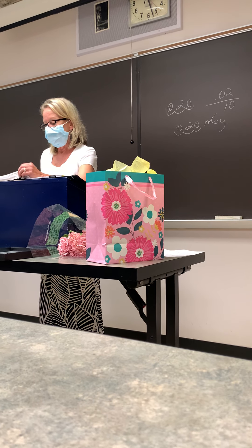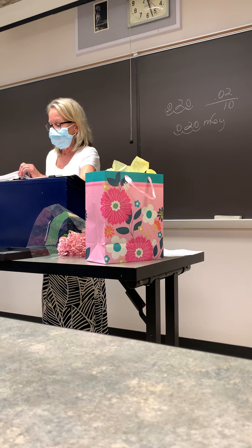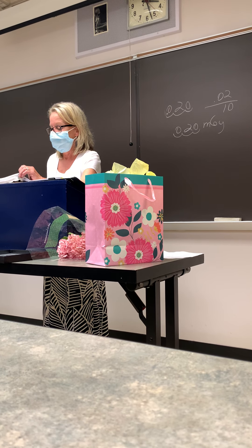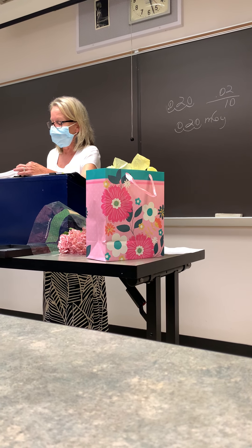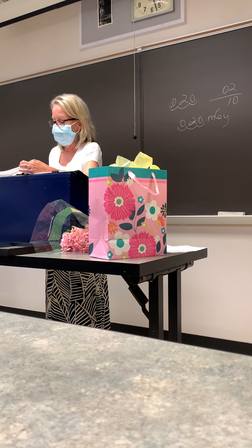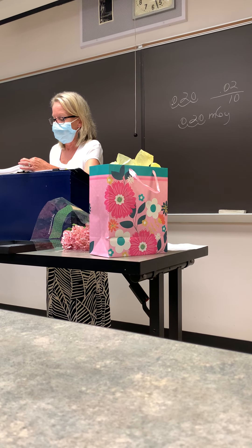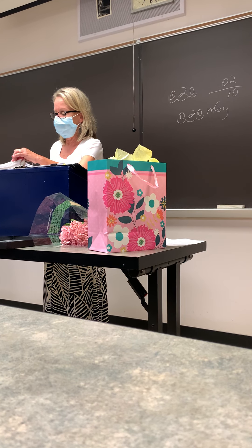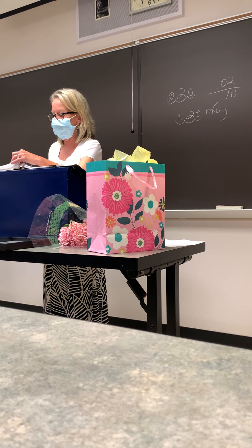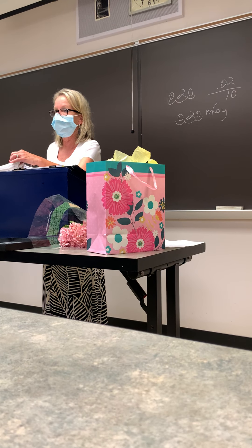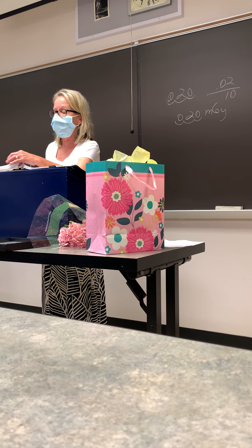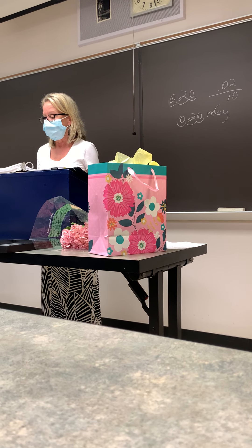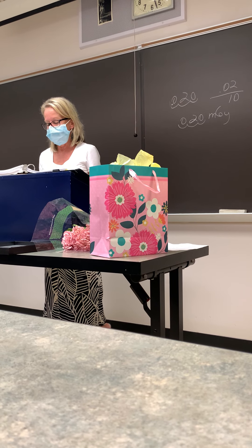Number eighty-two: a controlled area is defined as D — all of those. A controlled area always has an occupancy factor of one; there will be at least one radiation worker there.